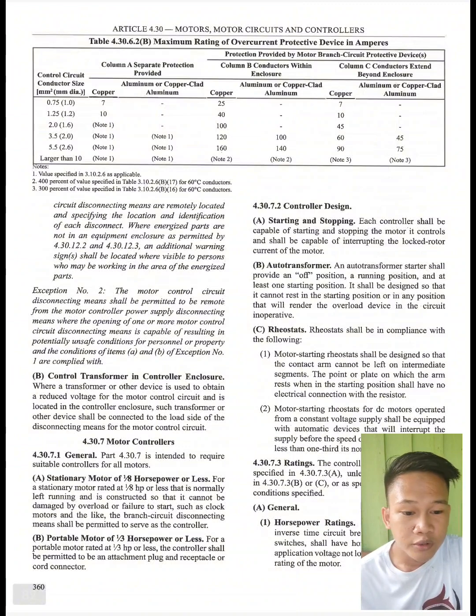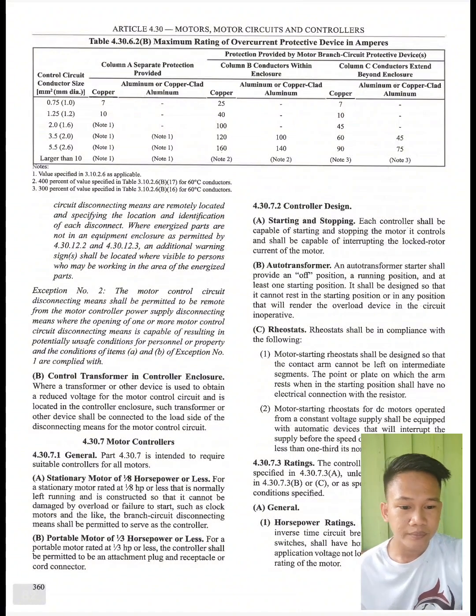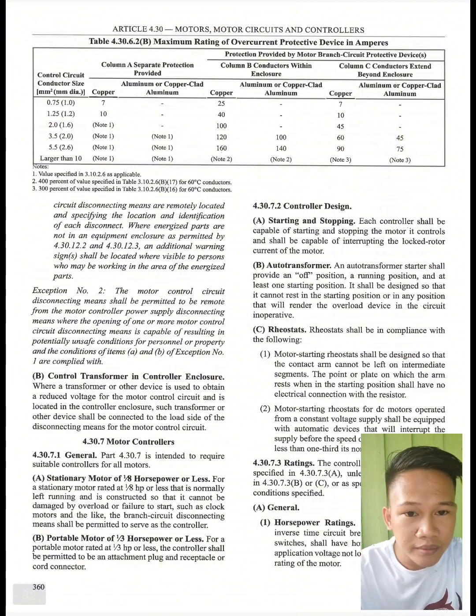B. Autotransformer. An autotransformer starter shall provide an off position, a running position, and at least one starting position. It shall be designed so that it cannot rest in the starting position or any position that will render the overload devices in the circuit inoperative. So third, C. Rheostats. Your rheostat shall be in compliance with the following. First, motor starting rheostats shall be designed so that the contact arm cannot be left on intermediate segments. The point or place on which the arm rests when in the starting position shall have no electrical connections with the resistor.